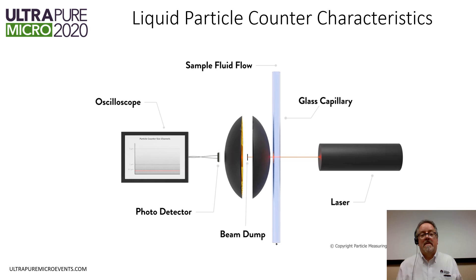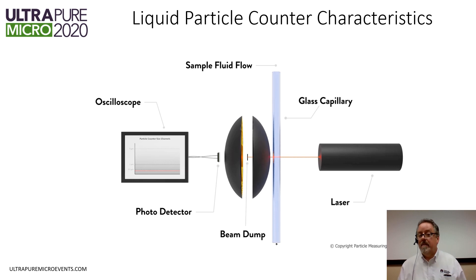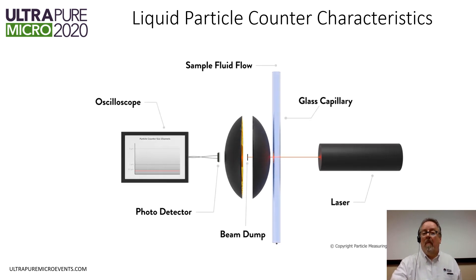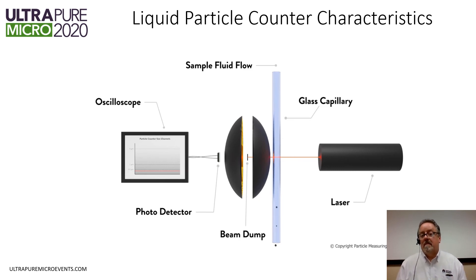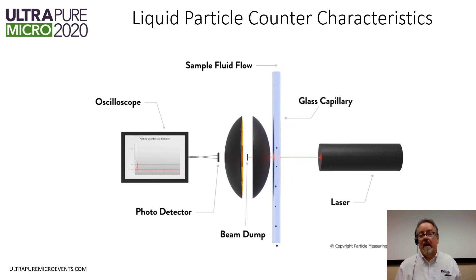This is a typical liquid particle counter. We have a light source — a laser — and a means of focusing the laser down to a flow capillary where the fluid that you want to measure is passing through. You have a means of collecting the scattered light that occurs when the particles pass through the laser beam, and you focus that light down onto a photodetector, which creates an electronic signal that you can measure.